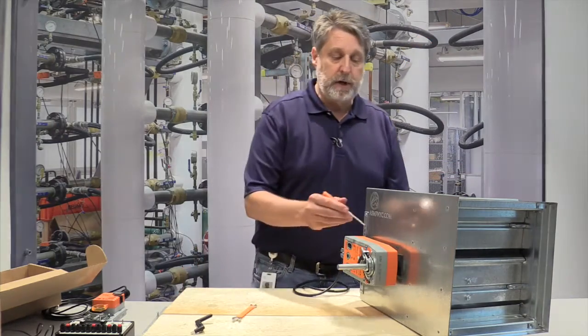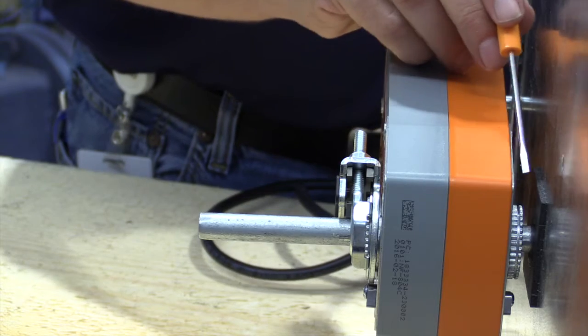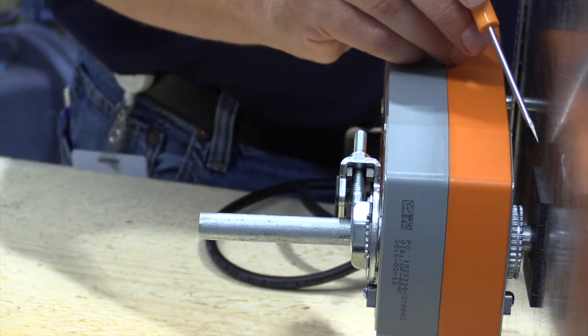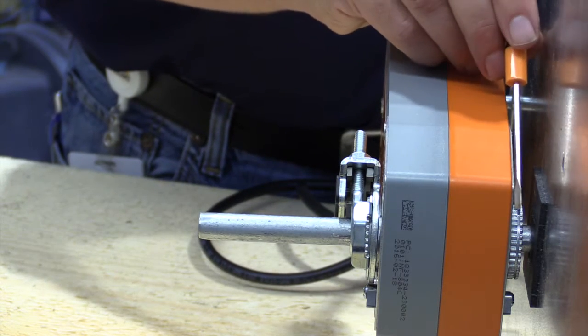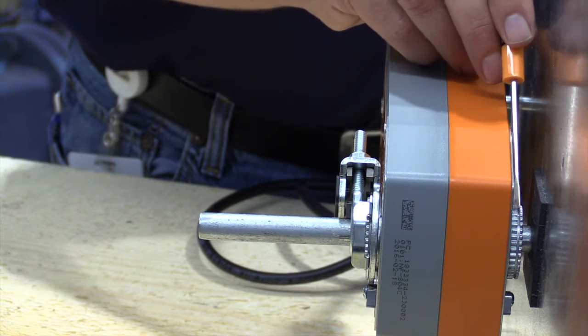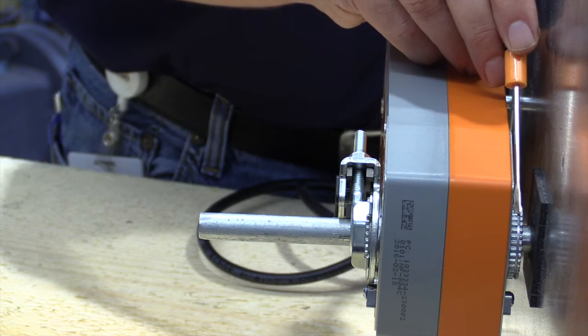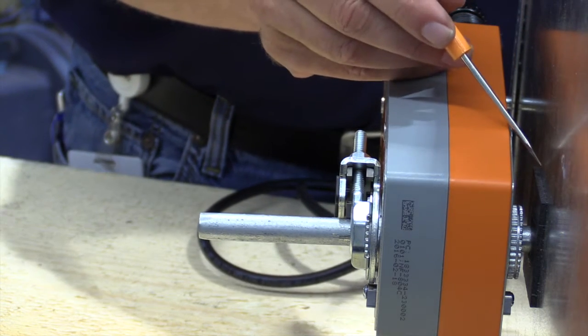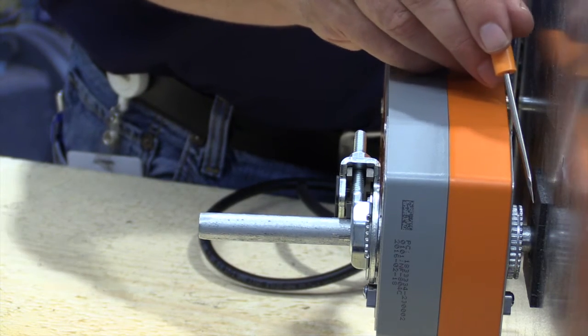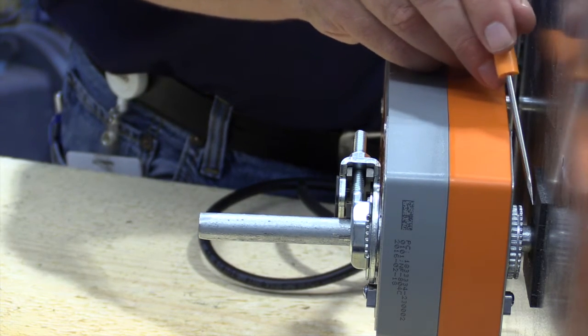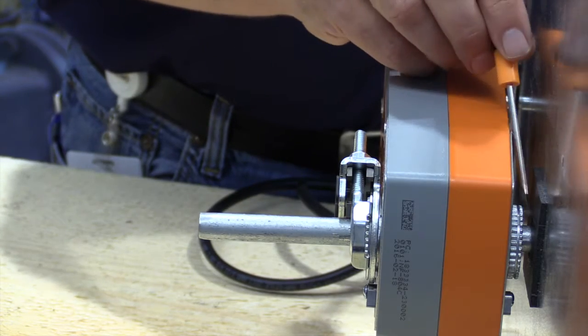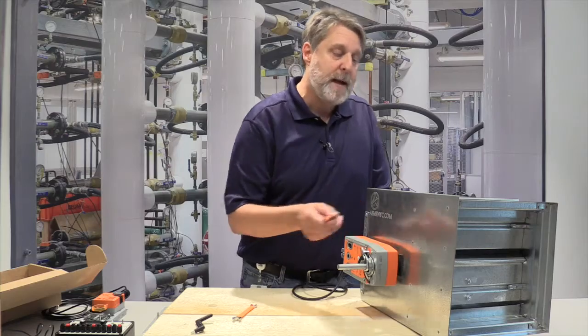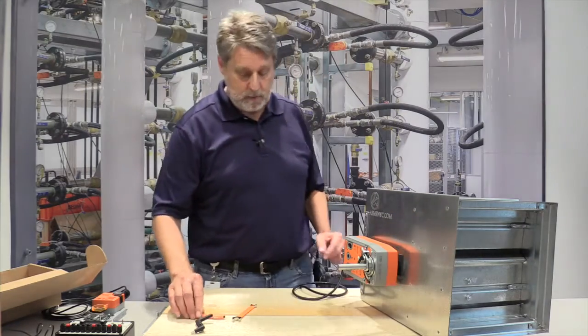Now, I want you to notice when I mounted the actuator, I left some space between the back of the actuator and the face of the ductwork. As this actuator is moving, the splines in the back are also moving and you would end up chewing up the face of the ductwork. In this case, there's a seal around the shaft and you would ruin that gasket. We always ask that you leave a little bit of space.